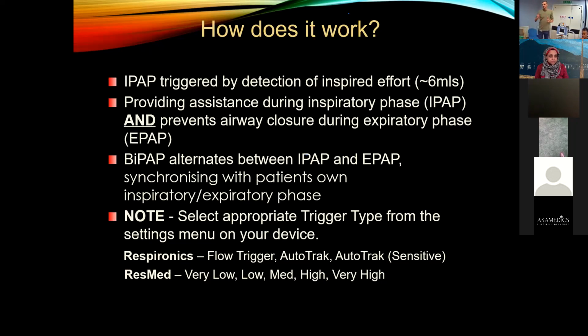So the machines that I've talked about that you guys are using, the ResMed and the Respironics. On the Respironics, within BiPAP, there's a setting called trigger type. Okay, so when we're in BiPAP mode, we would check all our settings, our IPAP, our EPAP, our FiO2. We'll talk about some of those in a minute. There's a setting called trigger type. Okay, you need to make sure you've got the correct trigger type selected. Okay, so with Respironics devices, we should select Auto-Trak. Okay, Auto-Trak is how the machine works most effectively, synchronizing with our patients. Okay, if you have patients with very low respiratory effort, you can use Auto-Trak Sensitive.